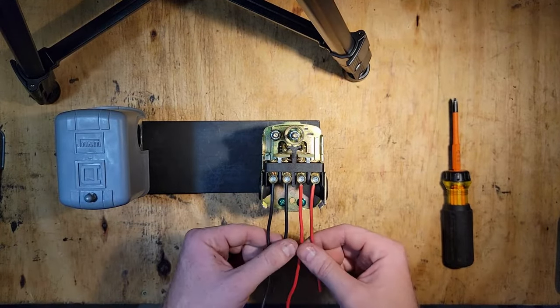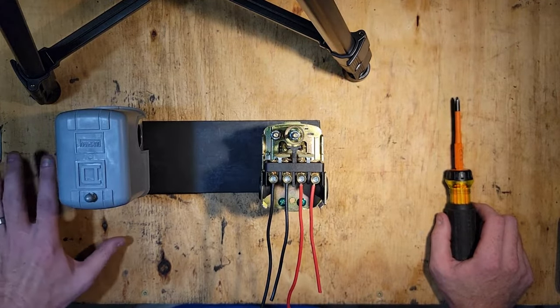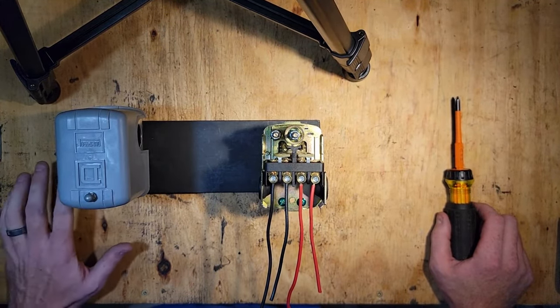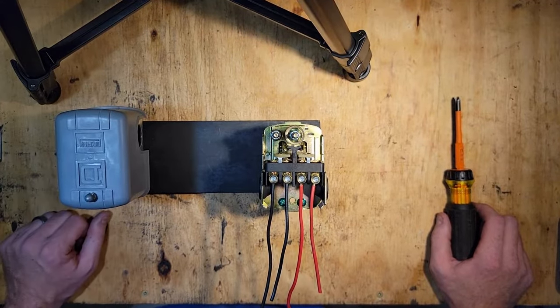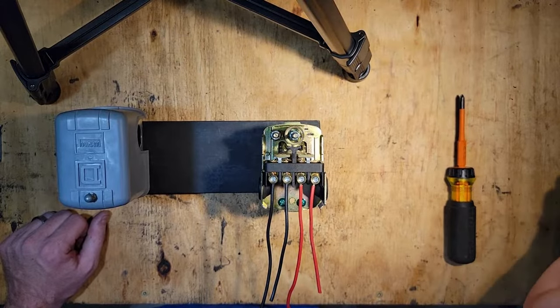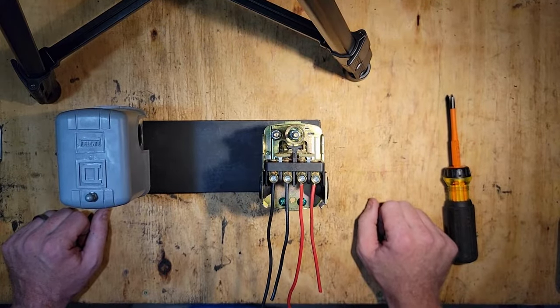So really, like I said, to start it all depends on what kind of control box you have and if you have a deluxe that has the switch terminal or you have a standard box that does not. Typically we see the horse and a half and larger control boxes have the option to be deluxe. It's really common in the three and five horsepower control boxes.